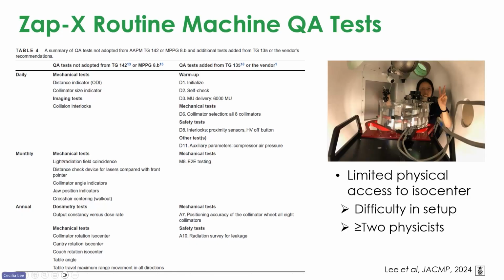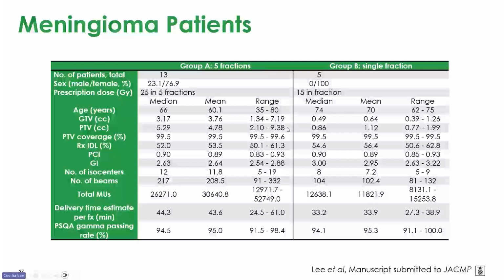You have to be on the table, for example, to set SSD or SAD. Then you have to be inside the unit or on the table. But if you are on the table, there is a table sag, so I like to be inside. That's the biggest challenge, and you always need someone else to help you retract the table or read the table position and gantry angle. So you cannot perform QA by yourself. Those were some challenges, but the majority of the time it's pretty straightforward and easy, and you can set up the phantom on the table and send it in. So we treated mainly meningioma patients, benign patients.